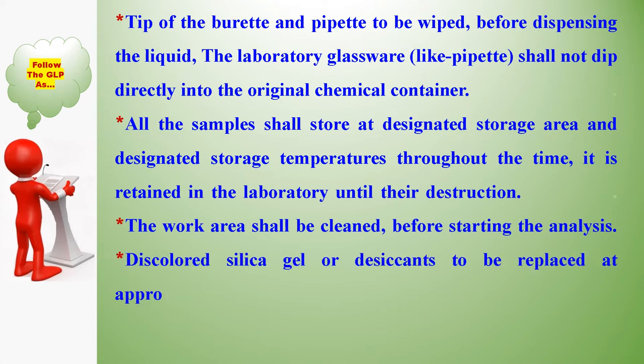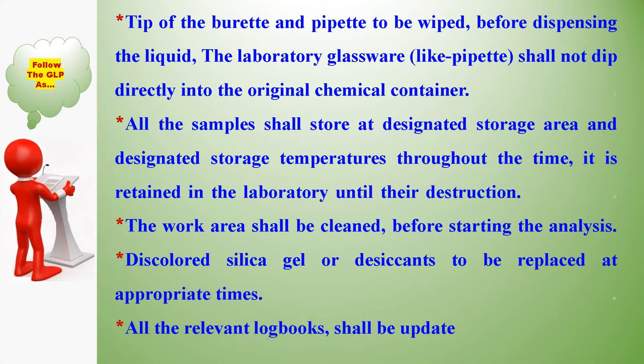Discoloured silica gel or desiccants must be replaced at appropriate times. All the relevant log books shall be updated concurrently.